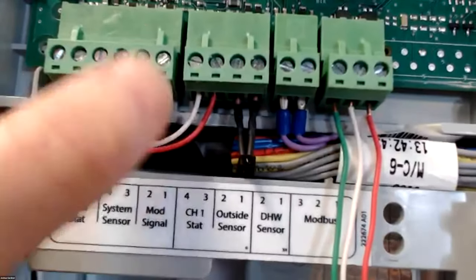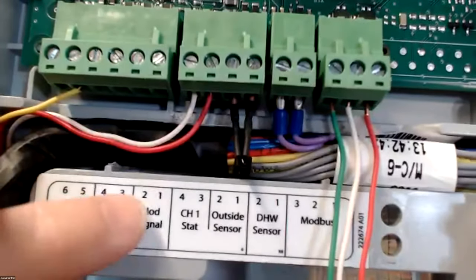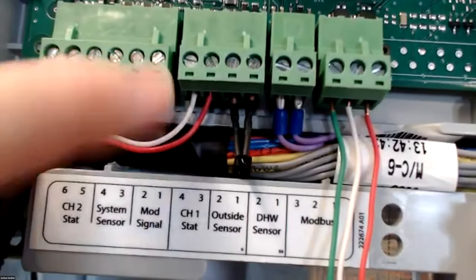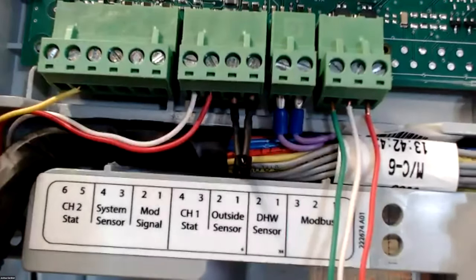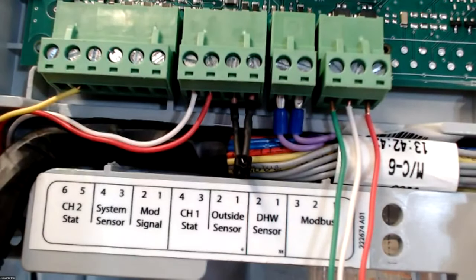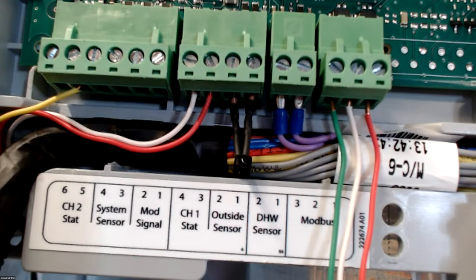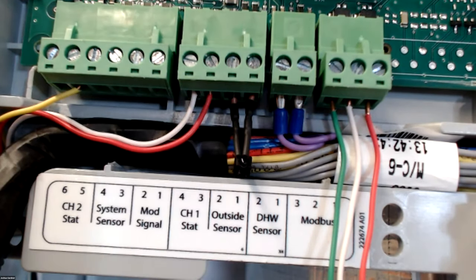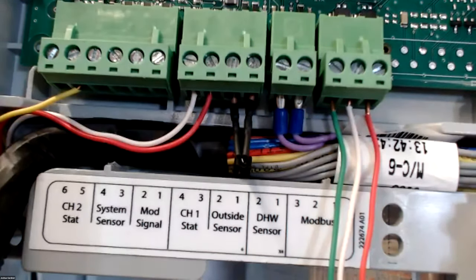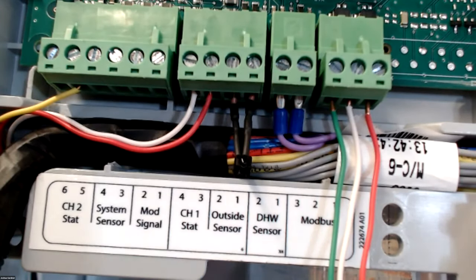Then our mod signal. So if you're using auxiliary modulation control, that will be connected into right here. And the next one is system sensor. Now, the sensor that comes with the boiler, that indirect sensor, can also be used as a system sensor. The system sensor is only being used if we're doing a cascading system. A cascading system requires a system sensor on the outlet of the secondary side on the supply, just as you're coming out of either the closely spaced tees or out of the low loss header.